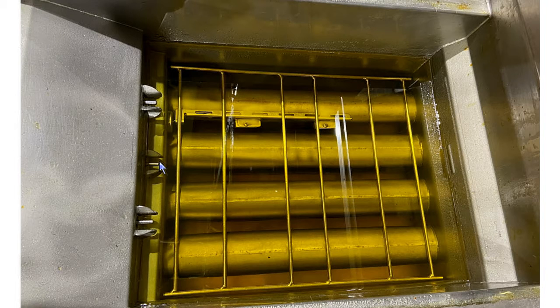So really what ends up happening is the control's doing everything it's supposed to do. We got our pilot flame sense, so then we have our voltage coming from our ignition module going back to our control board. Control board's closing a relay, allowing that 24, 25 volts to go out to the gas valve. Gas valve's opening up. It's turning the heat on, but we're never getting the input from our temperature probe because it's not in the oil. So that's the first thing you want to do.